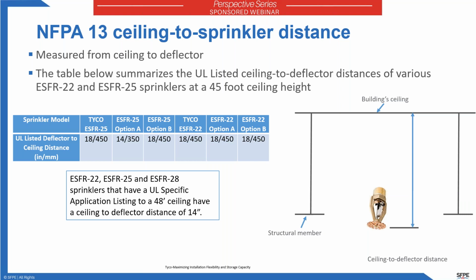So for instance, ESFR sprinklers, in addition to being approved to a 45-foot ceiling in NFPA 13 and FM 8-9, a number of sprinklers, there's an ESFR 22, the Tyco ESFR 25, and an ESFR 28, have UL specific application listing under a 48-foot ceiling. But one thing you should note is that at that ceiling height, all these three sprinklers are only approved to the 14-inch deflector distance. So I'm pointing this out to make you aware that the applications will drive some of the installation requirements for the sprinklers. So it's important. I can't reinforce this enough. It's important to read the literature that comes with the sprinklers to make sure that you're installing them properly.